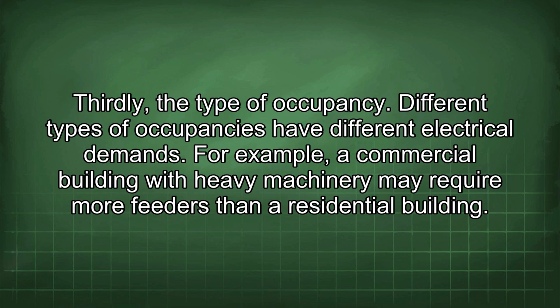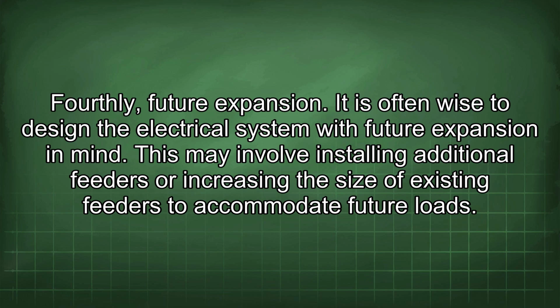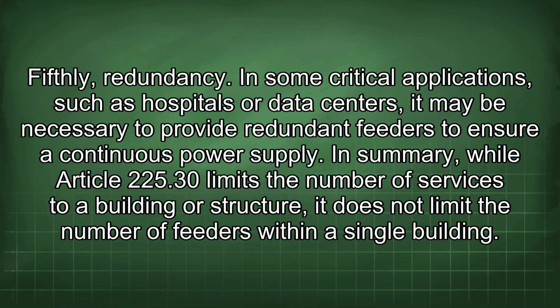Thirdly, the type of occupancy. Different types of occupancies have different electrical demands. For example, a commercial building with heavy machinery may require more feeders than a residential building. Fourthly, future expansion. It is often wise to design the electrical system with future expansion in mind. This may involve installing additional feeders or increasing the size of existing feeders to accommodate future loads. Fifthly, redundancy. In some critical applications, such as hospitals or data centers, it may be necessary to provide redundant feeders to ensure a continuous power supply.